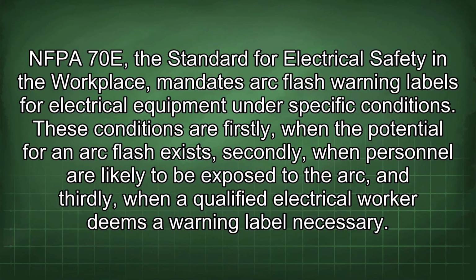NFPA 70E, the standard for electrical safety in a workplace, mandates arc flash warning labels for electrical equipment under specific conditions. These conditions are firstly, when the potential for an arc flash exists, secondly, when personnel are likely to be exposed to the arc, and thirdly, when a qualified electrical worker deems a warning label necessary.